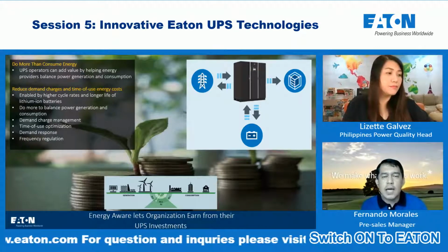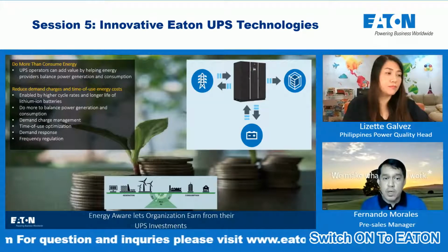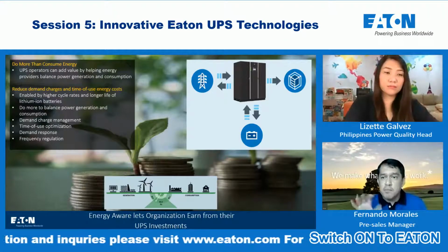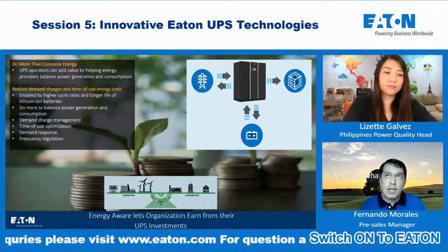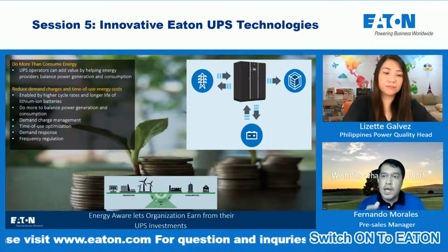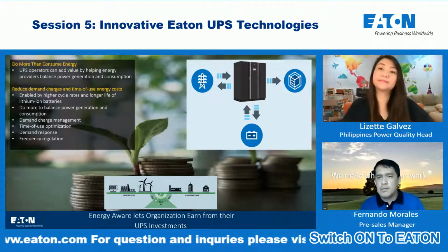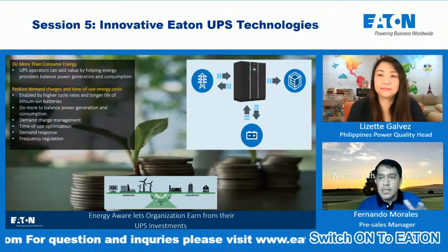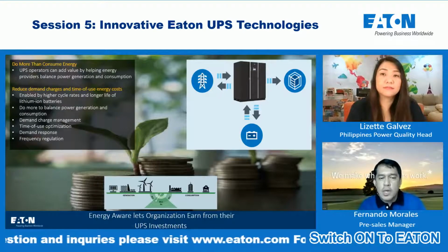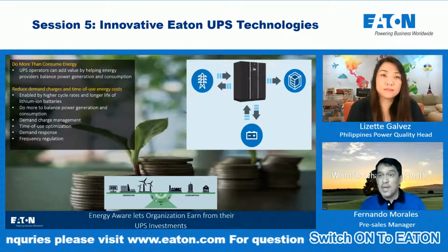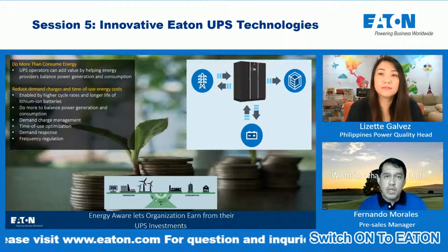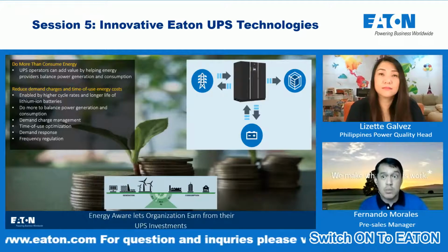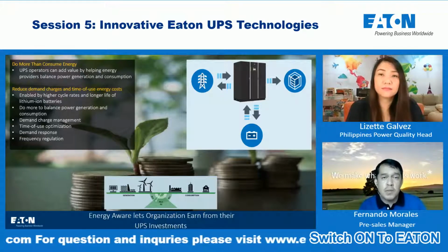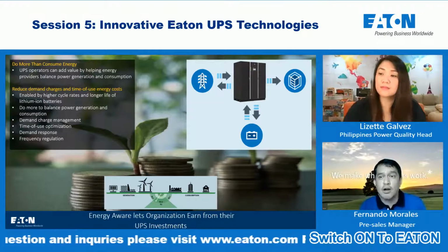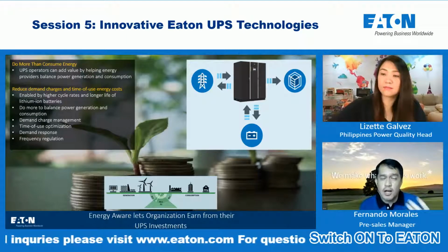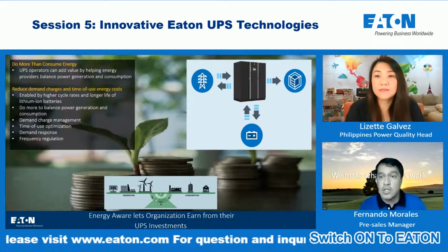We can also use it for time of use optimization. Meaning, if non-peak hours are, for example, between 3 p.m. and 12 midnight, just as an example, we can recharge the batteries of the UPS during this period. We all know that recharging the UPS battery consumes more power, but if we recharge it during off-peak hours, for example of Meralco, the customer will enjoy energy savings as well.